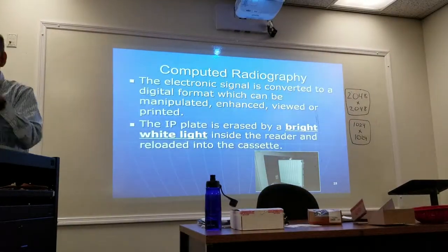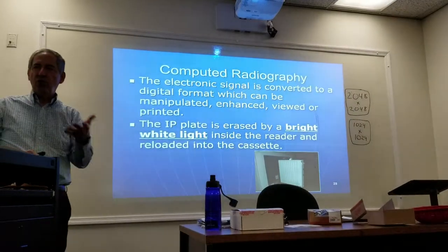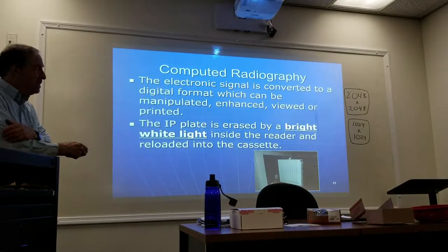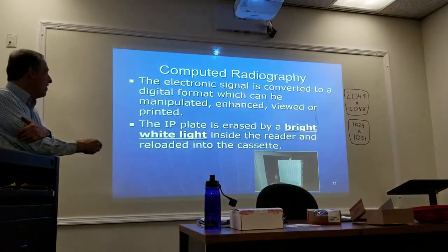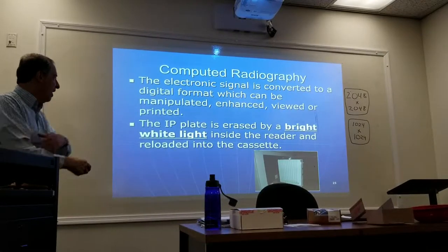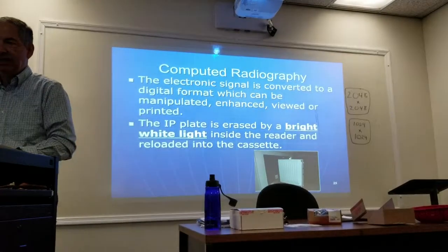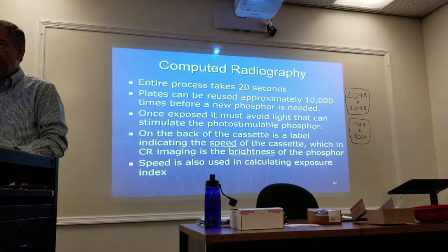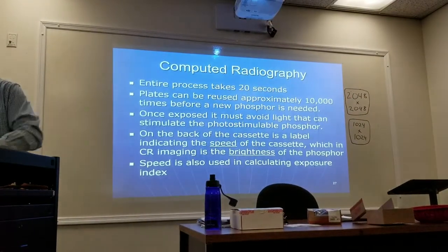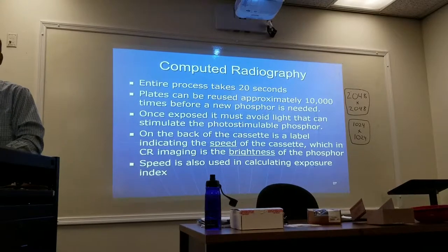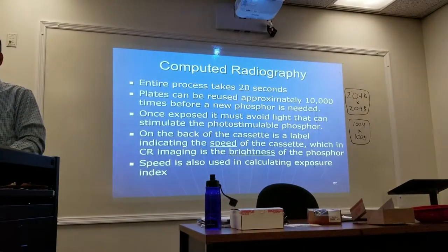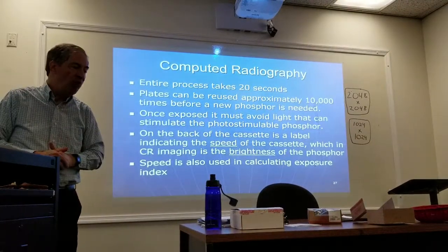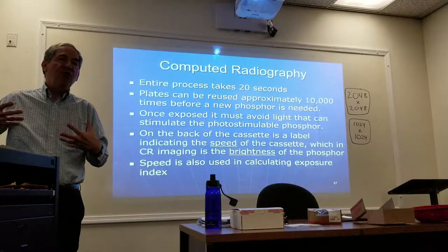The electronic signal is converted to digital format and manipulated. Importantly, the IP plate has to be erased using a bright white light inside the reader, and then it's reloaded. The whole process takes about 20 seconds. Plates can be used about 10,000 times, but once exposed, the plate has to avoid light so it doesn't stimulate those phosphors.